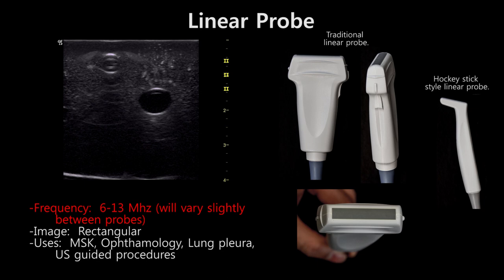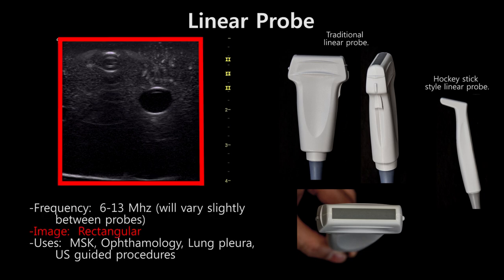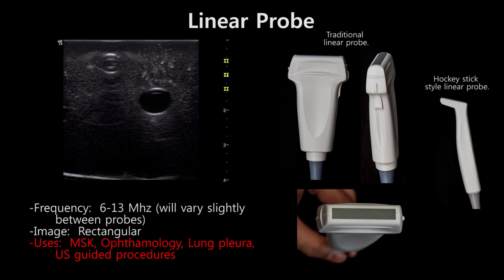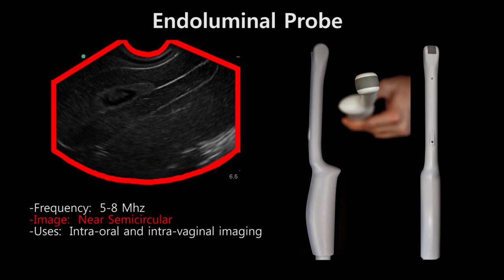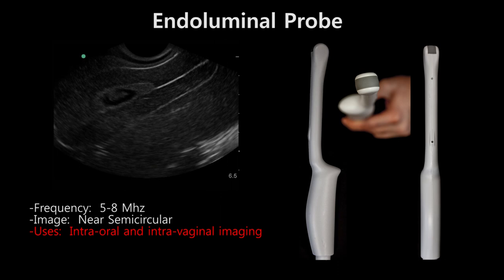The linear probe transmits between 6 and 13 megahertz frequency. It is characterized by high resolution and low penetrance. It gives a rectangular image and is typically used for musculoskeletal imaging, eye-orbit imaging, lung pleura imaging, and ultrasound-guided procedures. The endoluminal probe transmits at 5 to 8 megahertz frequency, with moderate resolution and moderate penetrance. It gives a semicircular image and is typically used for intraoral imaging and transvaginal imaging.